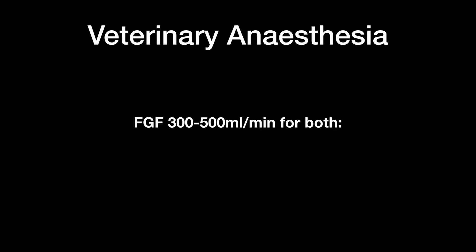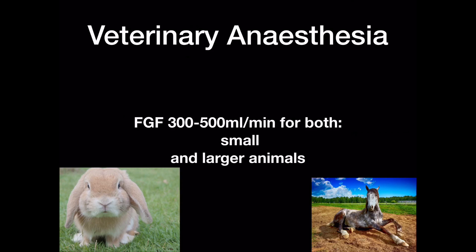Whilst veterinary anaesthesia is sadly beyond my expertise as a human anaesthetic doctor, I am reliably informed that it is possible to use a modified Humphrey ADE system that will allow the veterinary anaesthetist to use a fresh gas flow of 300 to 500 mL per minute for both small and large animals. If you are a vet and disagree with this, please do let me know, as it will be really interesting to get your perspective — the system appears to be mainly a historical one that is more popular in exams than in anaesthetic rooms in UK hospitals.